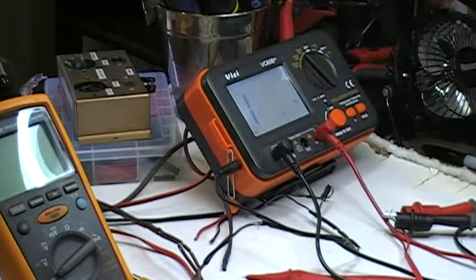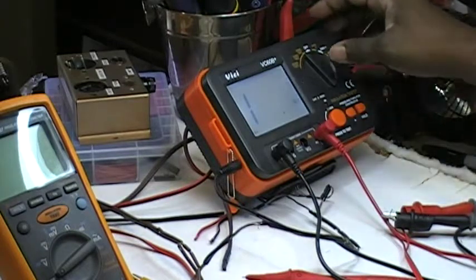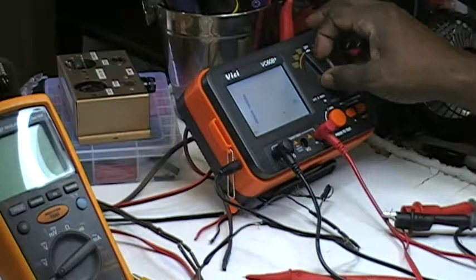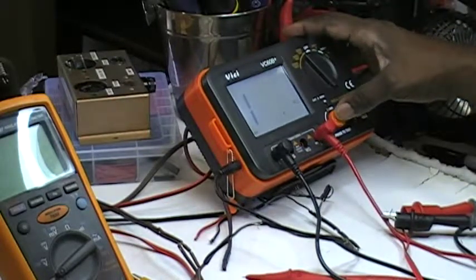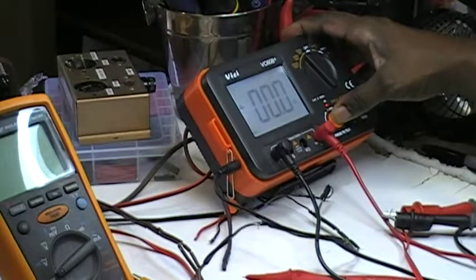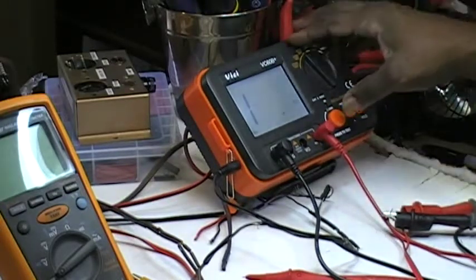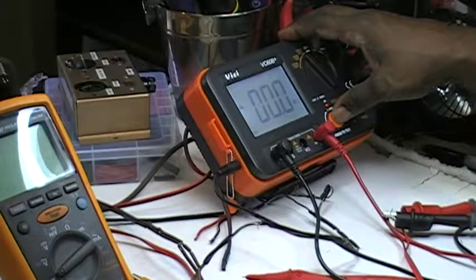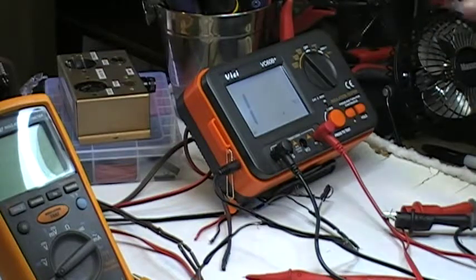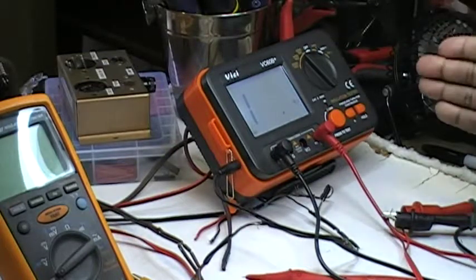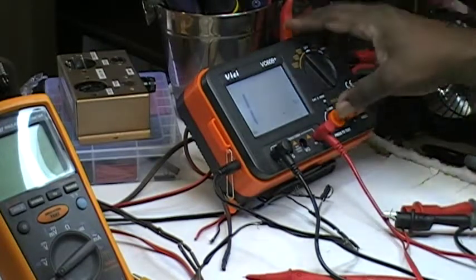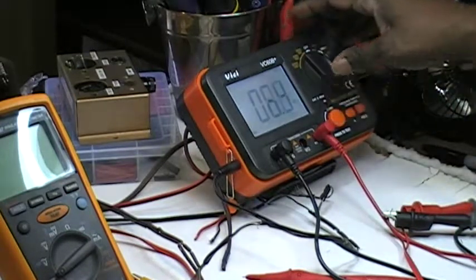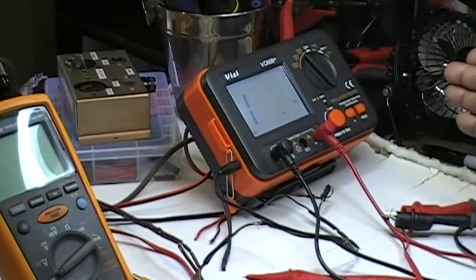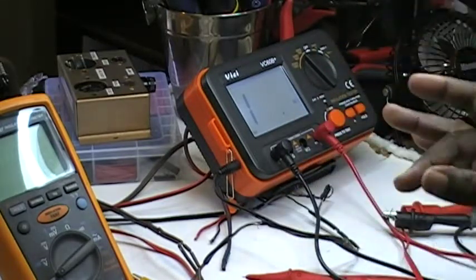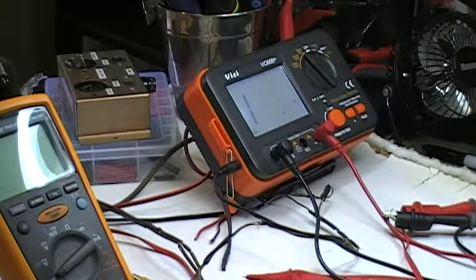So we want resistance. We have it set at 250 volts. I'm going to push the button. And there we got 19 megaohms. So this is a good wire. You saw the number jump up. Here we go, 55. So the number jumped up, giving us an indication that this is a good wire.